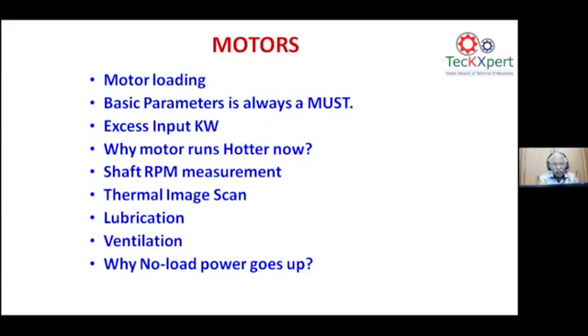As our Murugesan sir was telling, I am just giving a few examples and case studies where the problems are identifiable, or the parameters that are meant for identifying the problems in each and every part of the utility, from transformers to motors to compressors and other things. So, motor loading, basic parameters. See, motor loading is where we stand: less than 50, or around 50 to 75, or 75 to 100, or 100 and above.